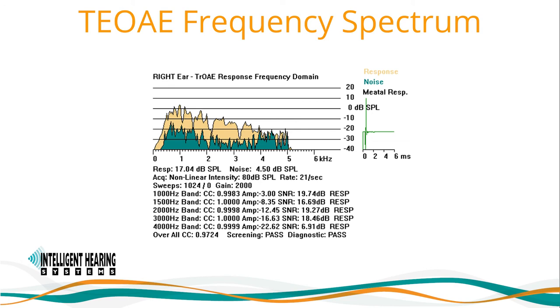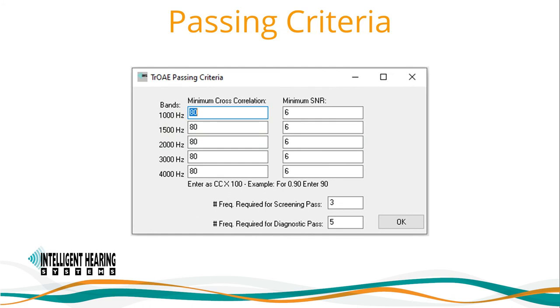Responses are typically present when threshold is less than 25 dB. The passing criteria is defined in terms of minimum cross-correlation and minimum signal-to-noise ratio. Values of 80 for cross-correlation and 6 dB for SNR are typically used. Cross-correlation data is the reproducibility of responses in buffer A and B — you are requiring the time domain response to repeat within itself at least 80%. A CC value of 1 means exact reproducibility. The second criteria is that the response amplitude must be above the noise amplitude by at least 6 dB. Responses are expected from normal middle ear and pure tone sensitivity of 25 dB HL. Responses are not expected from abnormal middle ear or cochlear hearing loss of 35 dB HL or greater.